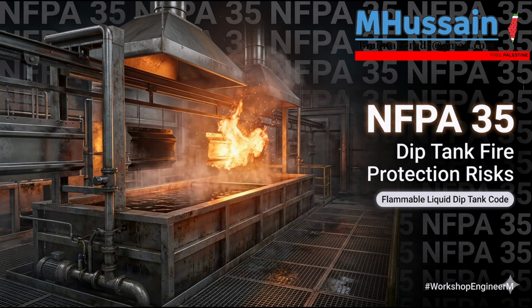pockets of vapor accumulation. But I have to push back on this from an owner's perspective. Think about the pure economics of this rule. The energy penalty. Yes, if I have a massive 50,000 square foot facility in Chicago in the dead of winter, I am mandated to pull 50,000 cubic feet of air per minute every single minute and blast it completely out of the building into the atmosphere. That's the rule. That air is heated. I paid to heat it. And to replace it, I'm sucking in 50,000 cubic feet of freezing, 0-degree outside air that I instantly have to spend massive amounts of natural gas to heat. The energy penalty is astronomical.